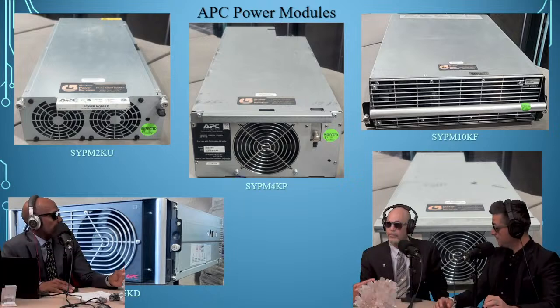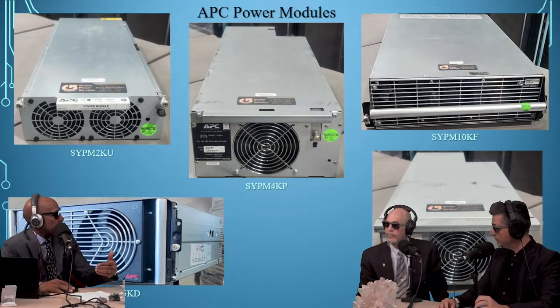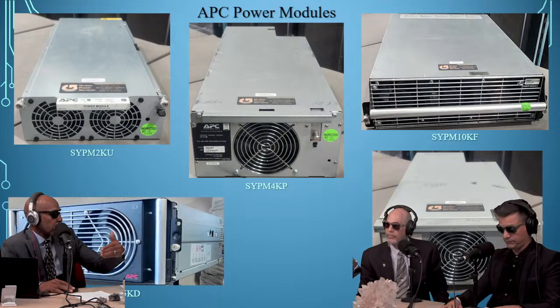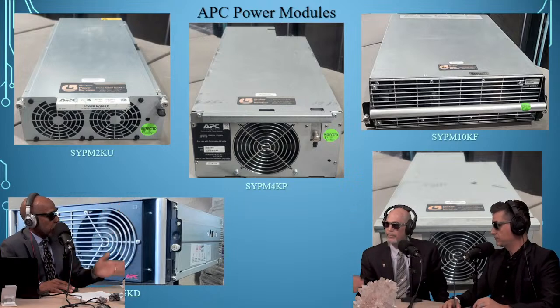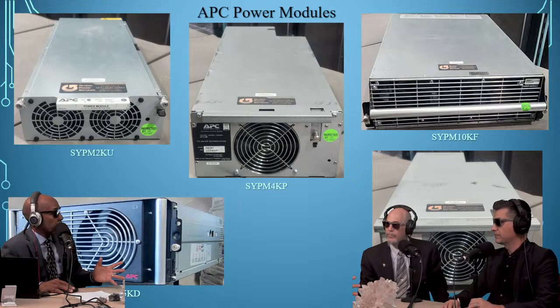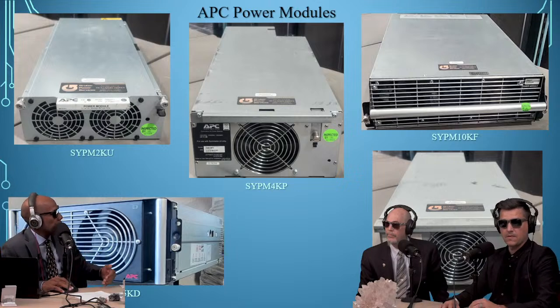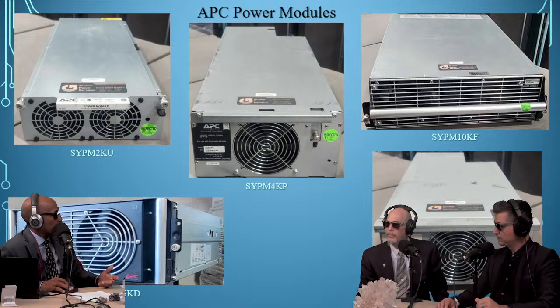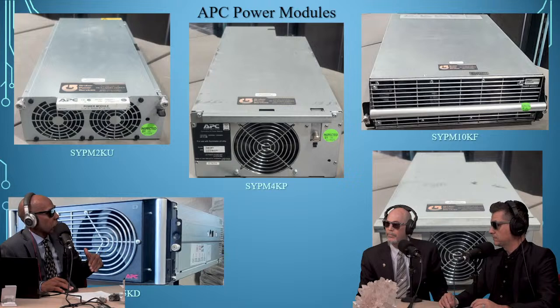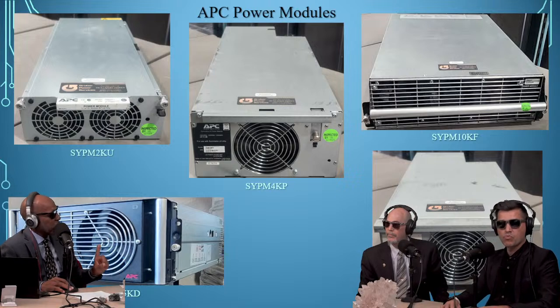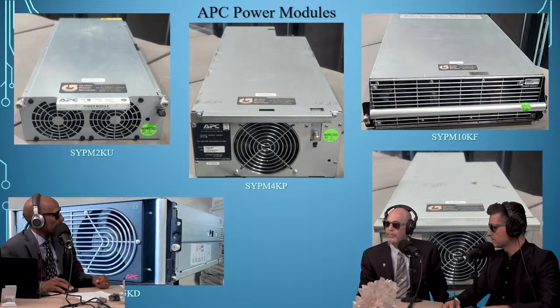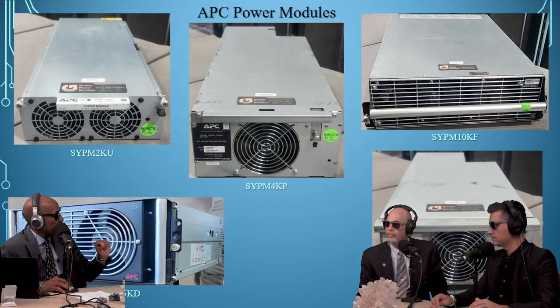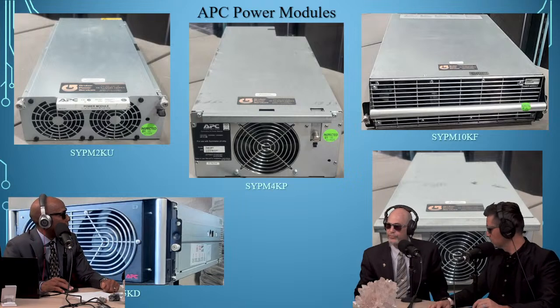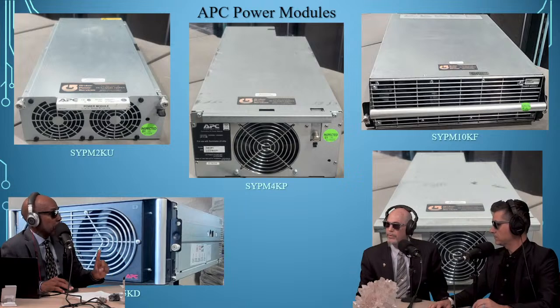His point is very valid, because on the back side, what we call the frame of the UPS, if you go to the back you'll see connectors up and down the frame. Those connectors are plastic—a tough plastic, but still plastic. If you misalign that power module because you don't know what you're doing, or you think you know what you're doing but really don't, you can break one of those plastic connectors or bend a pin. Guess what? Not the whole thing stops working—that's one of the beauties about it.